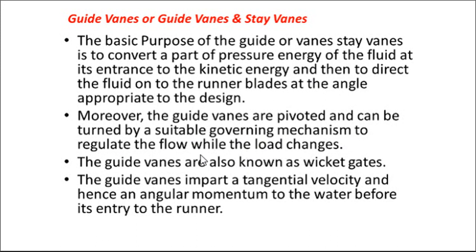while the load changes. Now see, the load on the turbine is nothing but electrical energy or electrical load. If the load on the turbine is high, then the shaft speed may decrease, but we have to maintain the speed constant because we want to maintain the frequency constant. So that's why the guide vanes are provided. If load is more, speed will be less, so you have to increase the flow of water. That can be done by opening and closing of guide vanes.